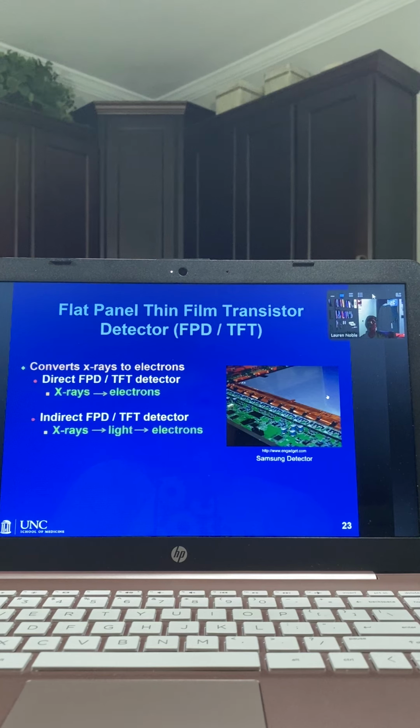So that's why the phosphor plate is considered to be an indirect detector, because we do have light involved in the process here. So that light that is given off by that phosphor plate in the reader will be collected by what device? What will collect that light? Because that's our image data.